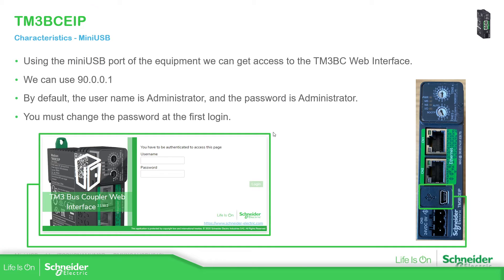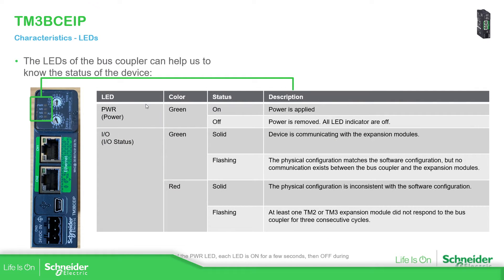As we saw in the past, we had the possibility to use the mini-USB of the Bus Coupler in order to open the Bus Coupler web interface. If we use this IP address in our browser, we should be able to access the web interface. You should use the administrator username and password, and then you must change the password. Once you are with the Bus Coupler, on the left part you have four LEDs. These LEDs give us information: if you have the power supply, this one will be on, and if you have something regarding the I/Os — the TM3 modules that come next to the Bus Coupler — you should check the I/O status LEDs. If everything is working fine, the green should be on. This is how you can identify where the problem is.